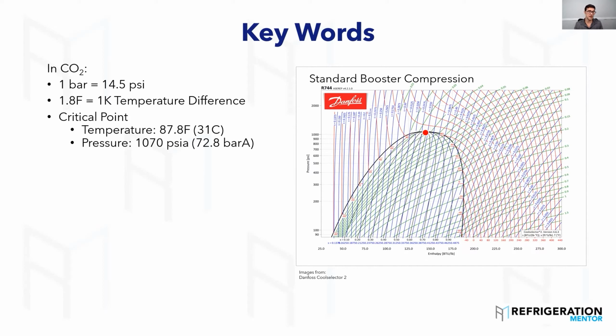And I've seen it many, many times. One of the trainers I used to work at, you could put it into transcritical and you could see that phase. You can change it from liquid to vapor to that transcritical. So it's important to know that because most ambients, most climates will get above that. Because CO2 was mainly in the regions where it's cooler out, like Canada was a great spot, anywhere north of the equator. When you start to get closer to the equator, it gets a lot warmer. So it was a lot harder to have CO2, because CO2 is not new. CO2 has been out for over 100 years in refrigeration.